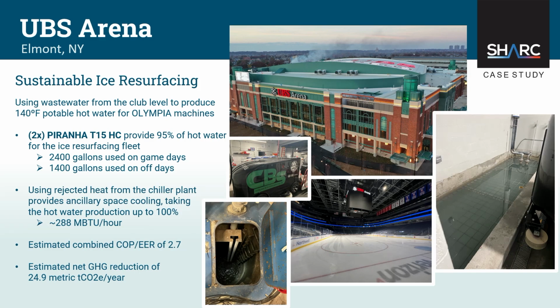They have very large Trane chillers to keep the humidity and temperature in the building perfect so the ice stays smooth. On dark days when there's nobody in the building, you can actually hear the chillers because they're ramped down so low. So now we're going to take some of that extra hydronic heat off the Trane chiller plant, run it through the Piranha HC, take that hot water production up to 100%, and also provide an additional 288 MBTU of cooling for the building. It's a win-win all around.